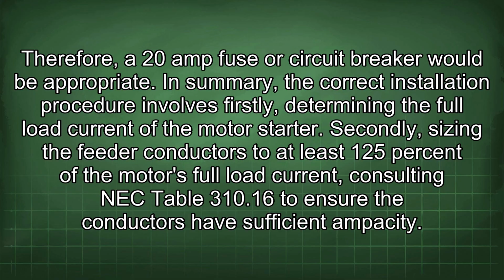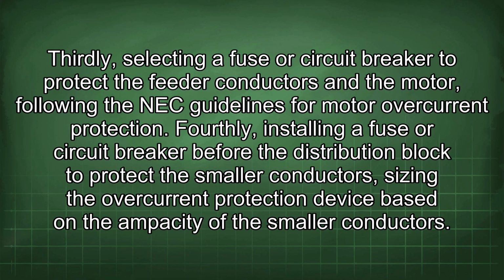In summary, the correct installation procedure involves firstly determining the full load current of the motor starter. Secondly, sizing the feeder conductors to at least 125% of the motor's full load current, consulting NEC Table 310.16 to ensure the conductors have sufficient ampacity. Thirdly, selecting a fuse or circuit breaker to protect the feeder conductors and the motor, following the NEC guidelines for motor overcurrent protection. Fourthly, installing a fuse or circuit breaker before the distribution block to protect the smaller conductors, sizing the overcurrent protection device based on the ampacity of the smaller conductors.